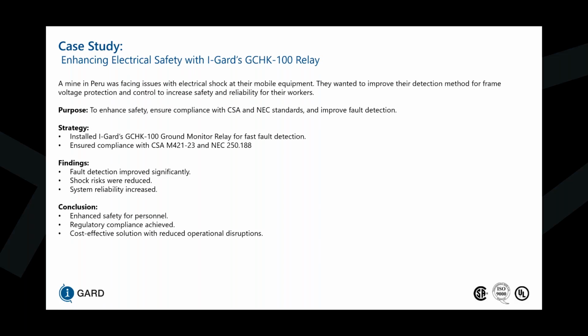So the case study of the use case for the GCHK 100 relay comes from a mine in Peru, which was facing issues with electrical shock at their mobile equipment, and they wanted to improve their detection method for frame voltage protection and control to increase safety and reliability for their workers. They also wanted to comply with CSA and NEC. So they installed the I-Gard's GCHK 100 for fast fault detection and frame voltage detection, as well as open short of the ground check connection. It ensured compliance with CSA M421 and NEC 250.